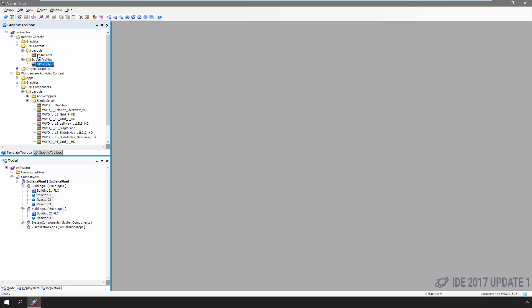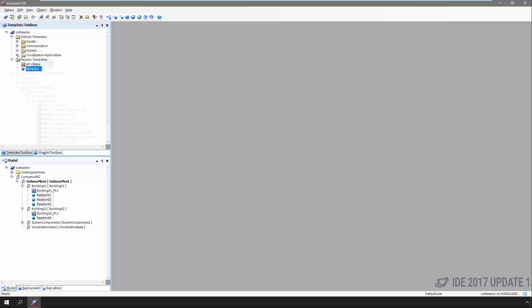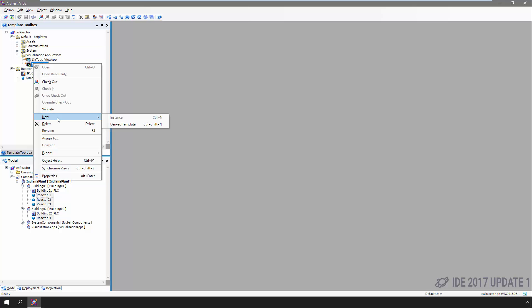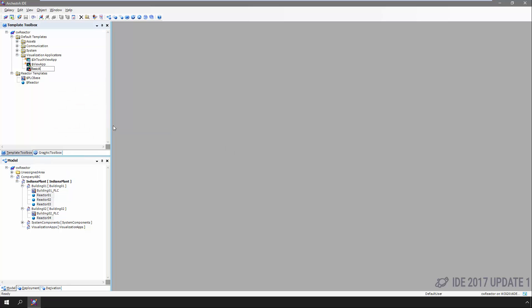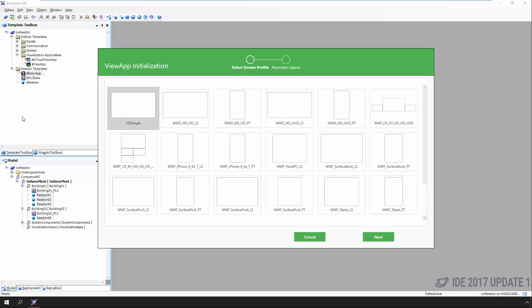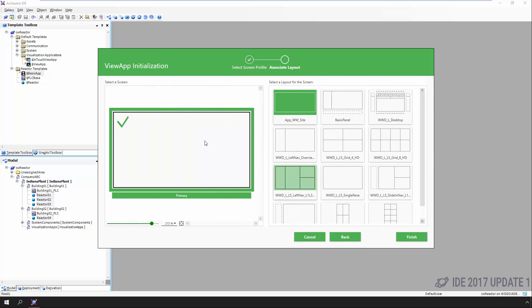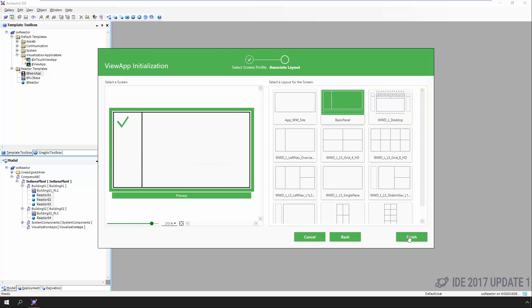What we haven't talked about is how these things relate to one another — how objects, screen profiles, and layouts are related. This is what we do in the InTouch OMI View App, the final new component within App Server related to InTouch OMI. The View App acts like any other object in a galaxy. We take the base template, create a derived template, give it a name, and double-click to configure it. The first thing we're presented with is the question of what type of screen layout we want this InTouch OMI application to run on. We select the single HD profile we created earlier, then select the layout we created moments ago, and click Finish.